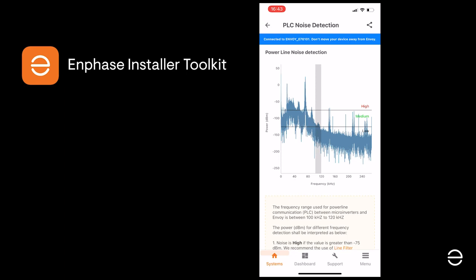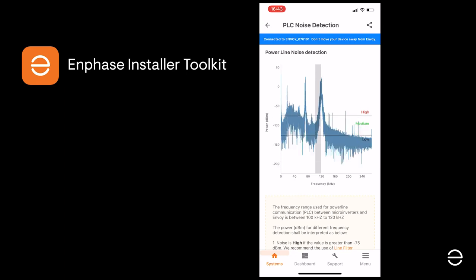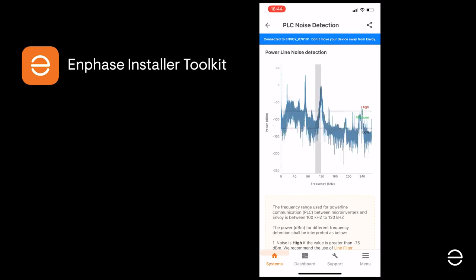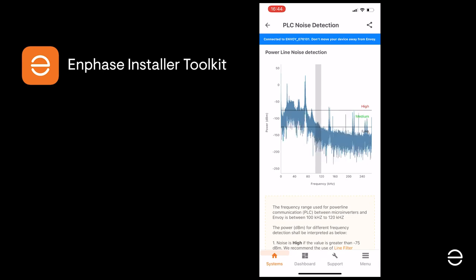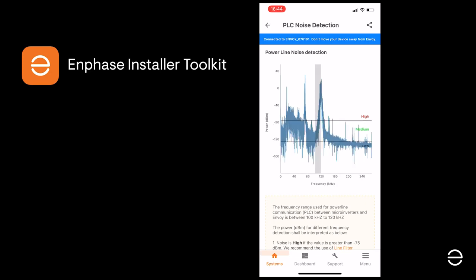When the blue lines are above the top horizontal line, there is a high level of noise, and when the blue lines are below the bottom horizontal line, noise is weaker. Ideally, the blue lines should be within the two horizontal lines. Please refer to the Enphase manual to correct noise if you see that there is a clear anomaly.